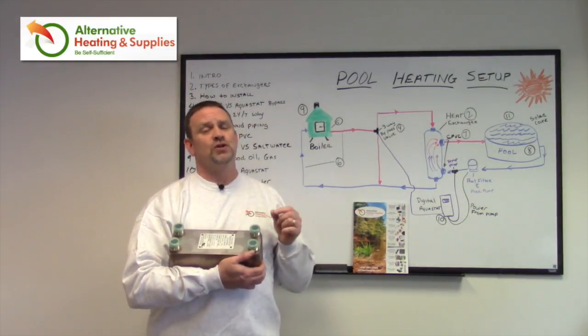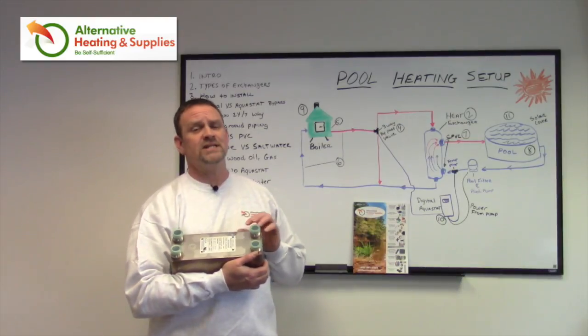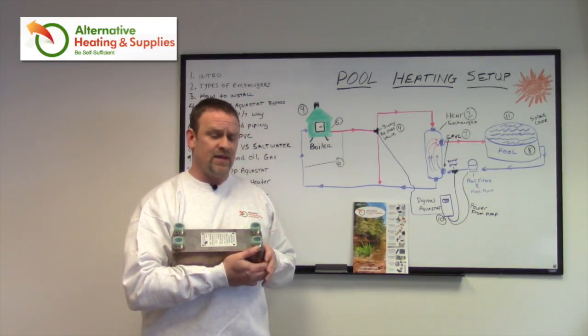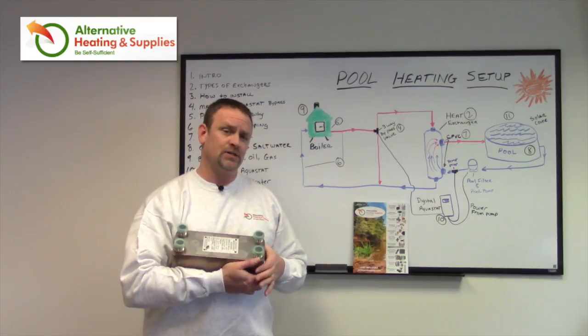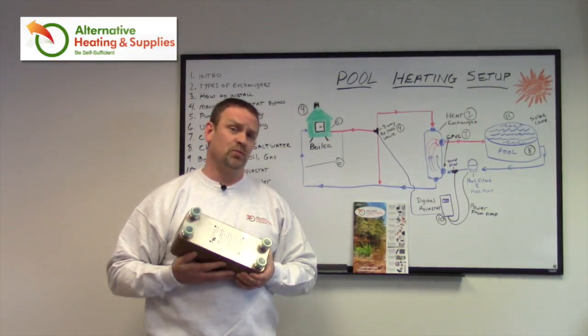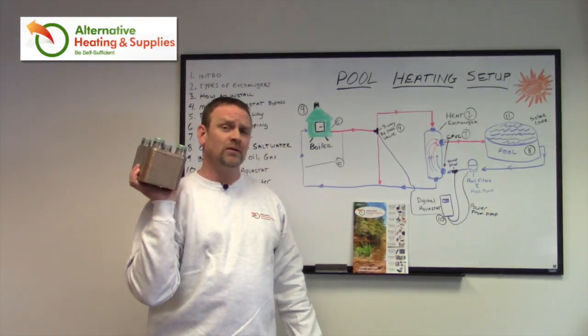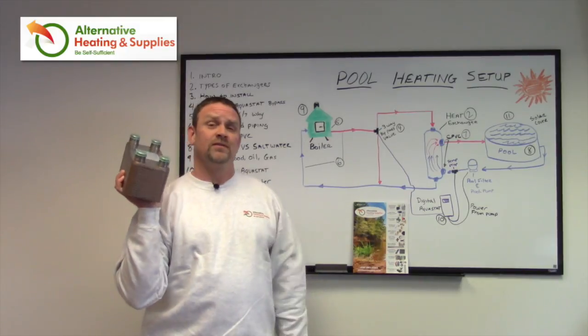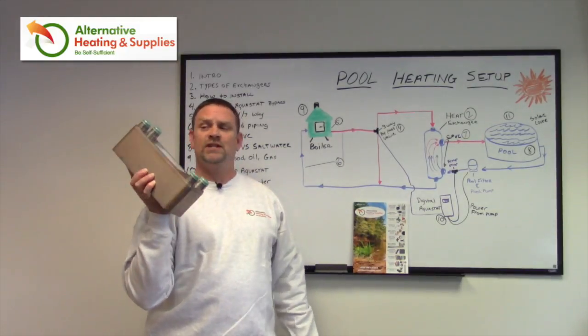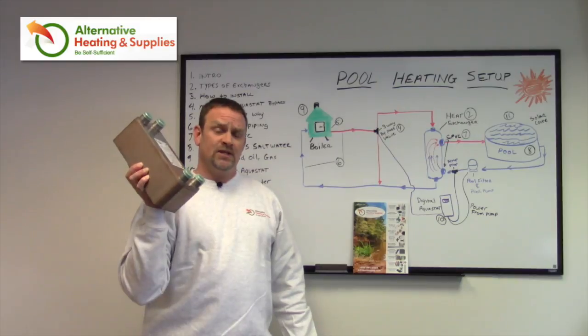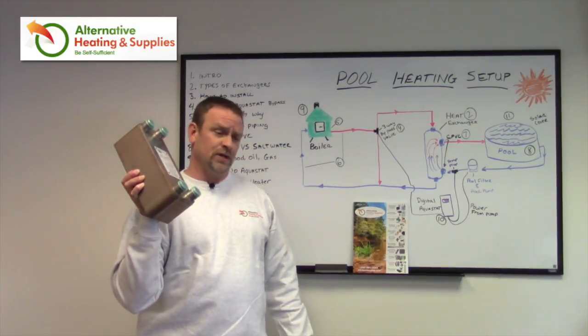The other problem is they're usually brazed. And when the brazing is done with copper, that will also be eaten by the salt water or the chlorination in the pool. So again, these will last quite a while, but they do not last as long, because they're not designed to do this. These are designed to heat up with boilers inside and also domestic hot water heaters.